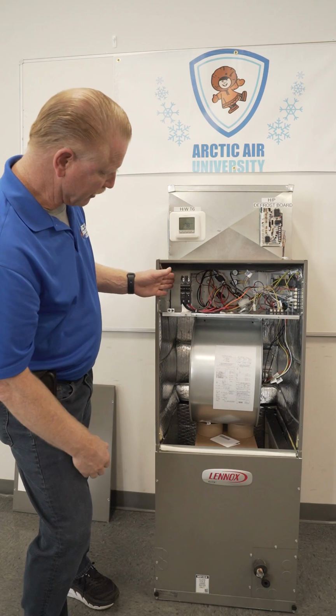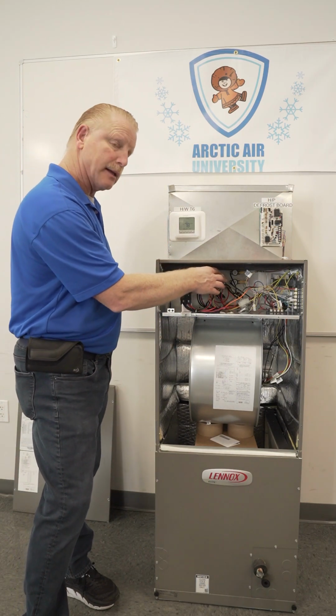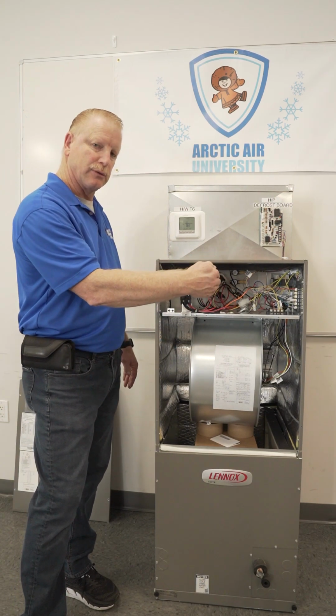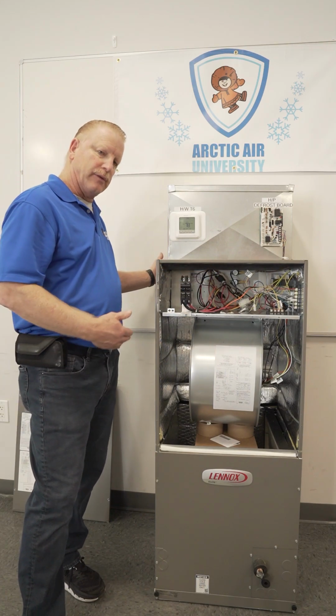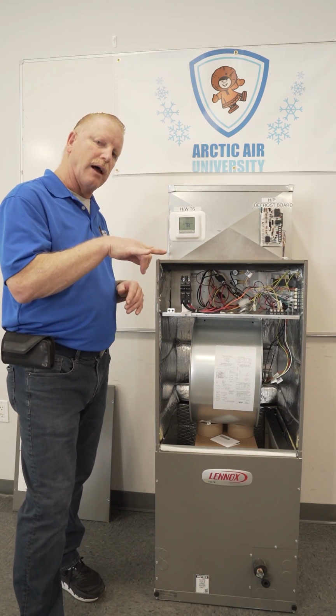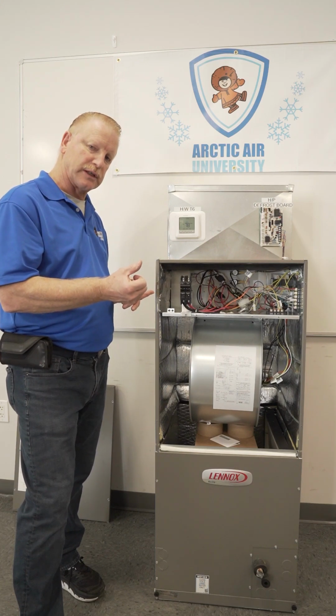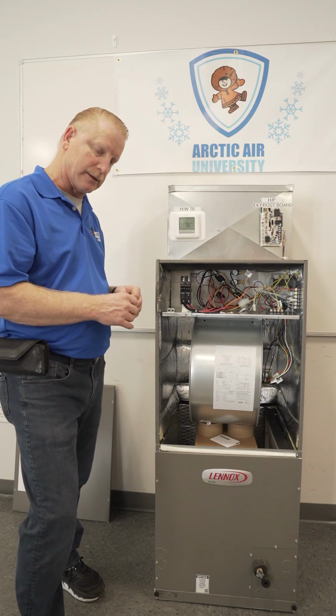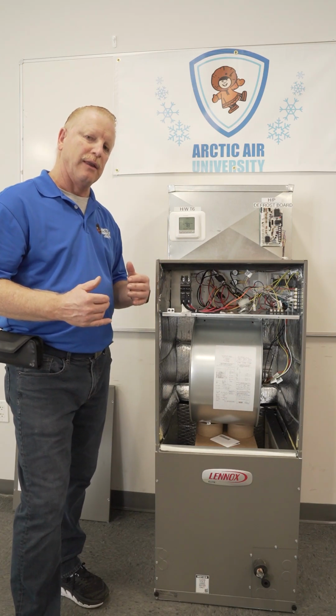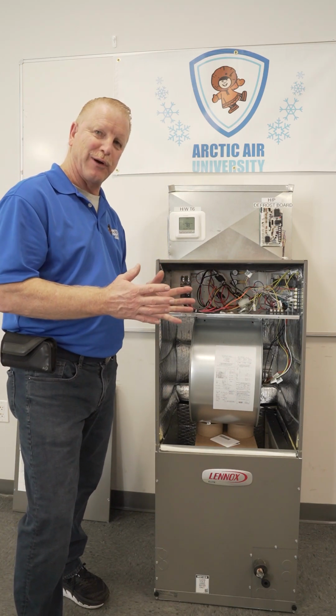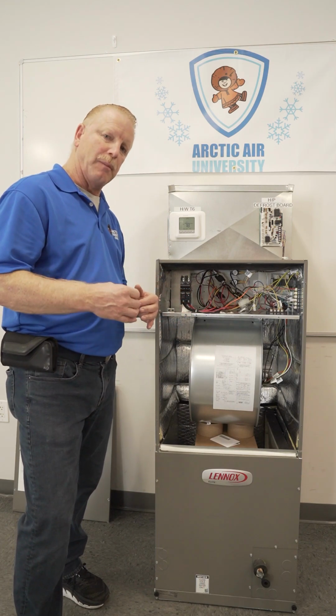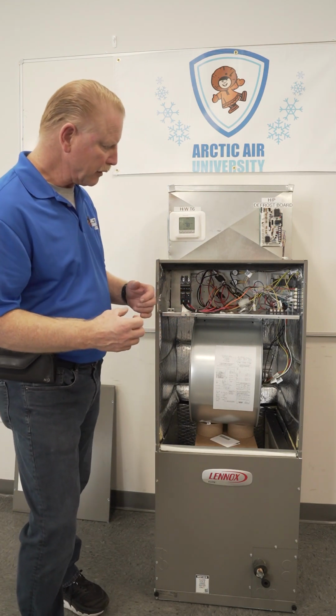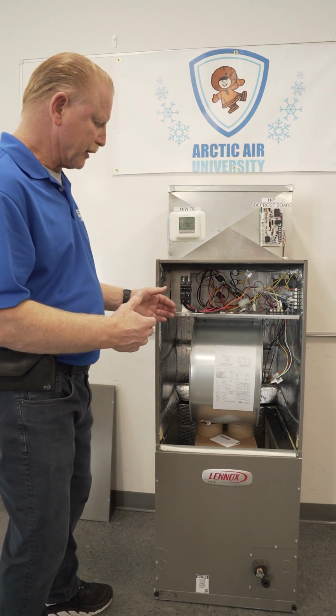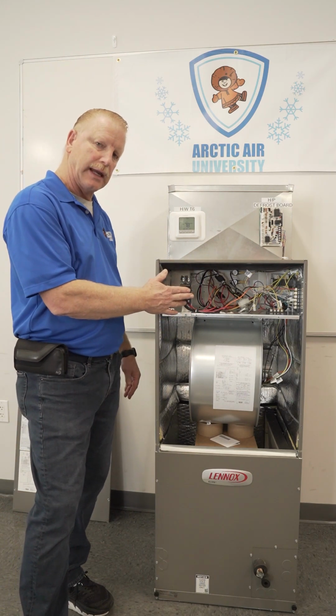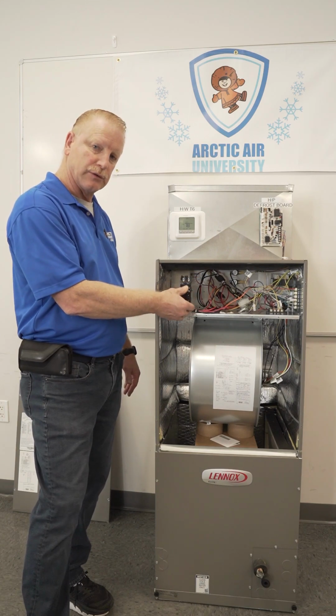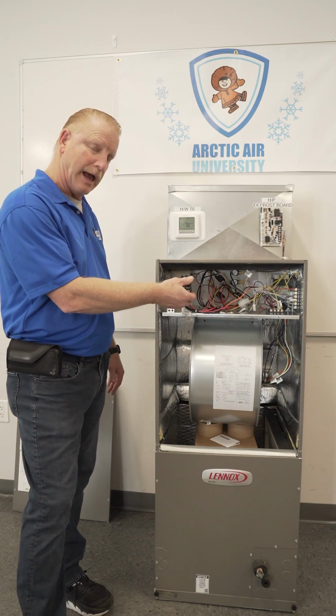Now, screws come with the package for the strip heaters. You slide the strip heat section in there and screw that in place. In the back of the unit, there's two holes that line up and help secure the strip heaters in place. If you're not sure what strip heaters are, think of the toaster that we toast our bread or bagels in every day, but on a much larger scale, okay? After that, they're secure. Some units, the larger the kW, could have their own circuit breaker. This one happens to have it.